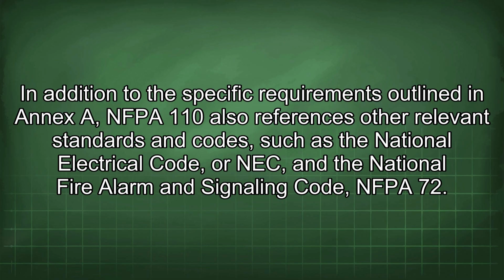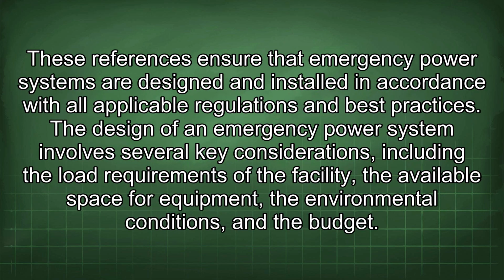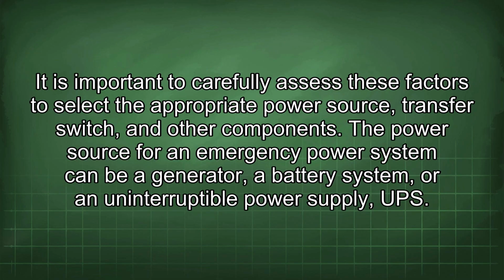In addition to the specific requirements outlined in Annex A, NFPA 110 also references other relevant standards and codes such as the National Electrical Code, or NEC, and the National Fire Alarm and Signaling Code, NFPA 72. These references ensure that emergency power systems are designed and installed in accordance with all applicable regulations and best practices. The design of an emergency power system involves several key considerations, including the load requirements of the facility, the available space for equipment, the environmental conditions, and the budget. It is important to carefully assess these factors to select the appropriate power source, transfer switch, and other components.